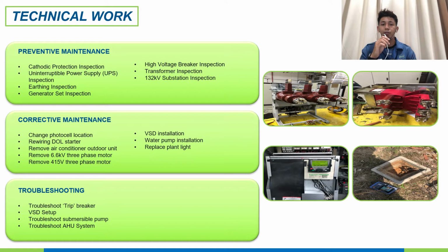So, what am I responsible for in technical work? We have three types of technical work, which are preventive maintenance (PM), corrective maintenance (CM), and troubleshooting. Preventive maintenance is the regular and routine maintenance of equipment or assets in order to keep them running and prevent any costly unplanned downtime. In PM, I did CP protection inspection, UPS inspection, earthing inspection, genset inspection, high voltage breaker inspection, transformer inspection, and 132 kV substation inspection.